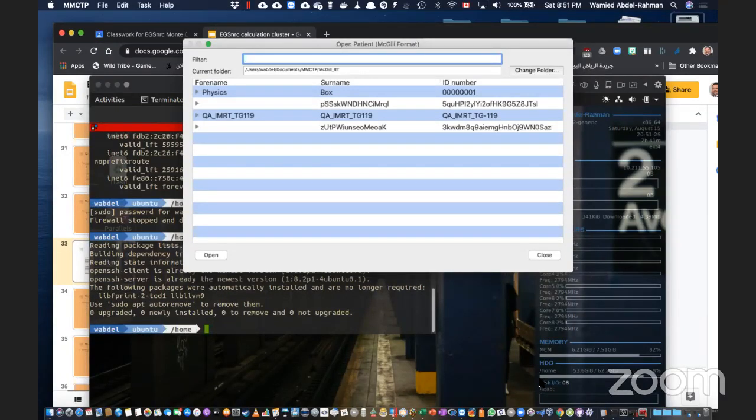Well, for radiotherapy, if you have something new, the first thing you need to do, if you want to use Monte Carlo, is validate or generate a Monte Carlo model, a beam model that represents the treatment unit. If that is cobalt, a MV Linac, or even an orthovoltage machine, you need to generate a beam model first, so that you can use the beam with it.